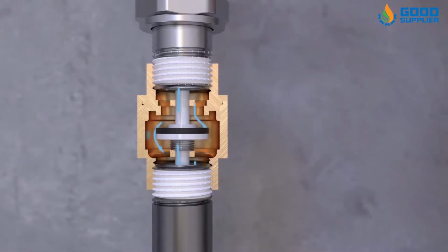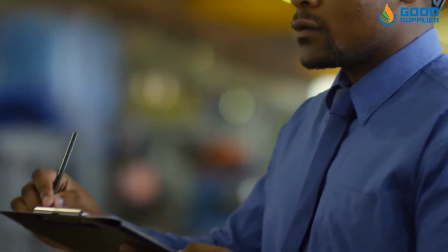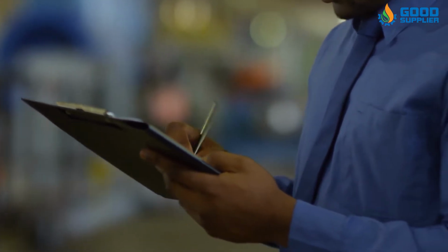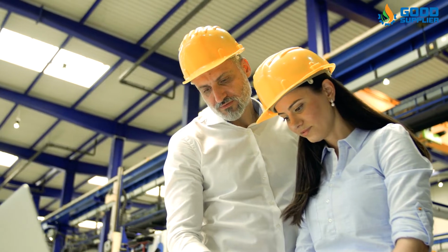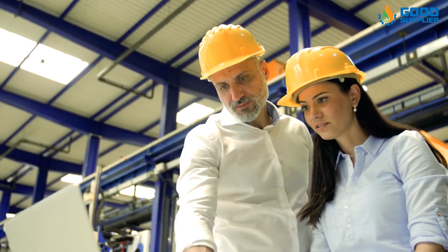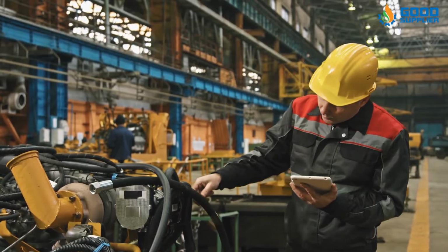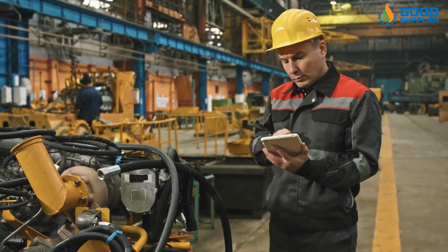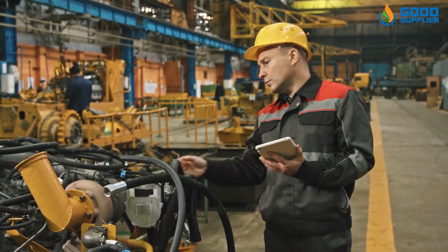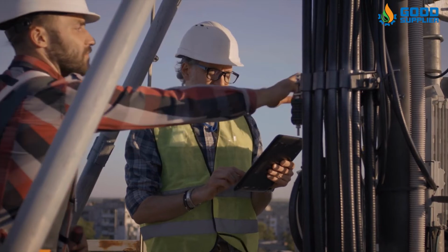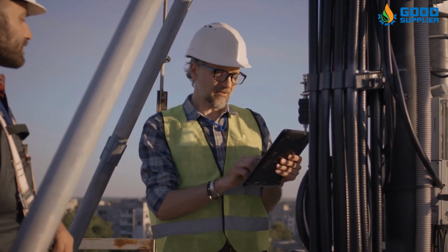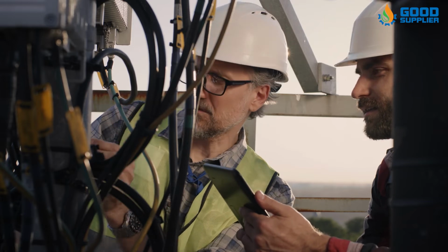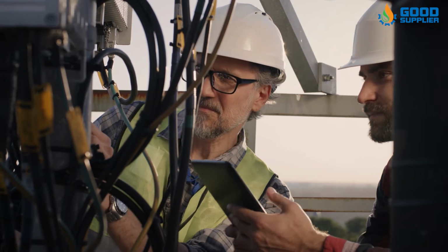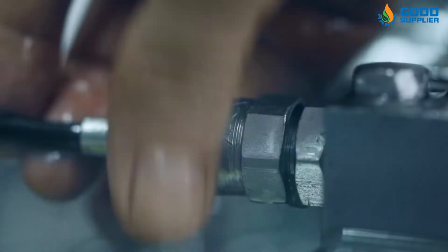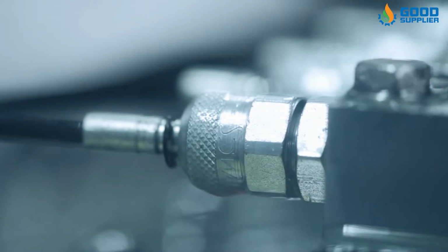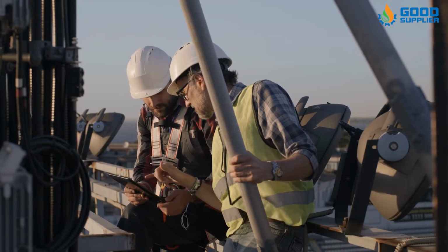water in the pipes. When choosing a check valve, it is essential to make a cost-benefit analysis of the specific system. Often, the focus is to reduce cost and, at the same time, obtain the lowest possible pressure loss, but when it comes to check valves, a higher safety equals a higher pressure loss. So, to ensure the check valve protects the system adequately, each design must be assessed individually. Factors such as the risk of water hammer, acceptable pressure loss, and the financial consequence of installing a check valve with a too high safety margin against water hammer have to be considered.